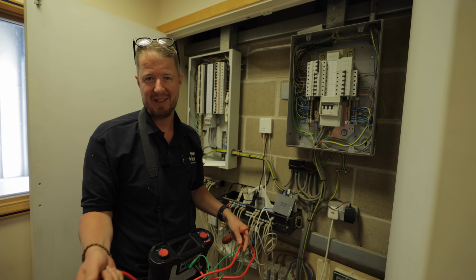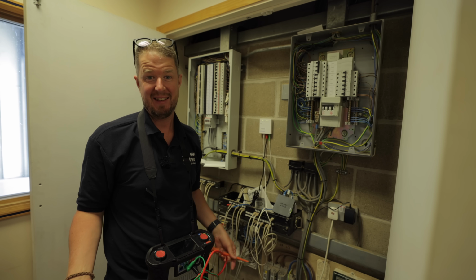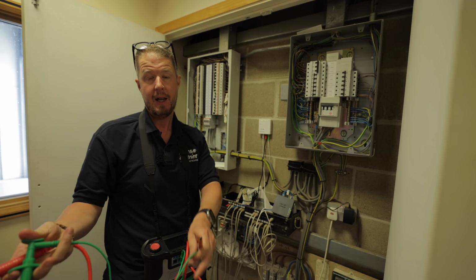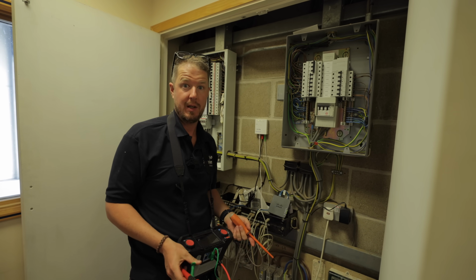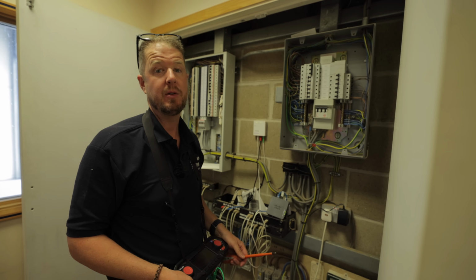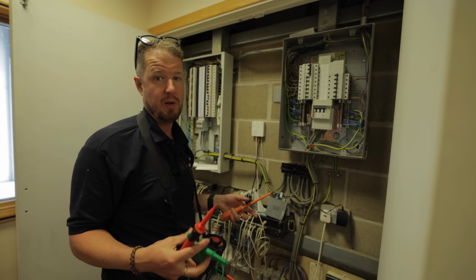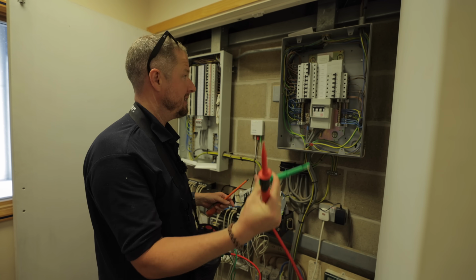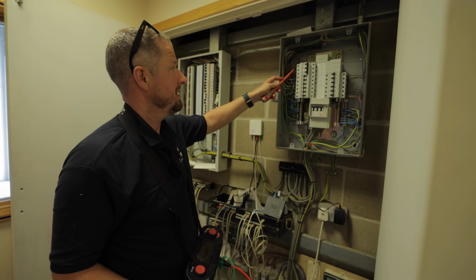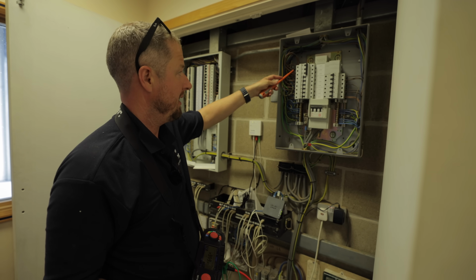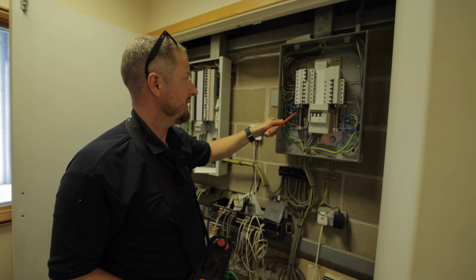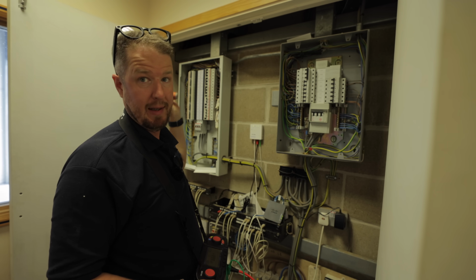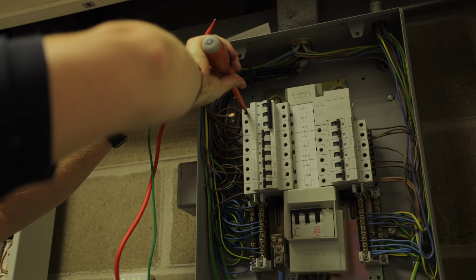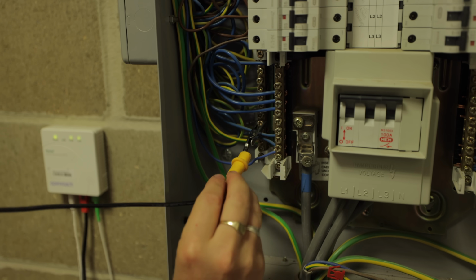So now that we've recorded all of our circuit details, the next thing is to start doing some actual testing. So we're going to do our dead tests, which are starting with the R1 and R2 test. That's the earth continuity or continuity of CPC. And to do that, we need these two leads. And what we're going to do is disconnect the line conductor here from the breaker, make a link to the earth bar, and then we're going to test it at the end of line on the circuit. So we're going to start with circuit 1, and that's the roller shutter door.